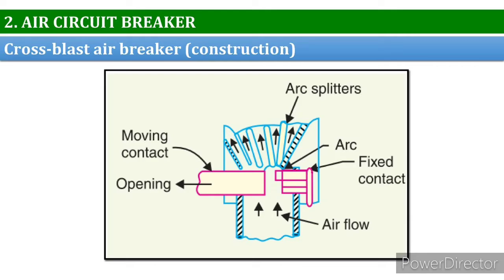When the moving contact is withdrawn, an arc is struck between the fixed and moving contacts. The high-pressure cross blast forces the arc into a chamber consisting of arc splitters and baffles. An important distinction is that the final gap for interruption is large enough to provide normal insulation clearance, so a series isolating switch is not necessary. However, the cross blast design is more complex compared to the axial blast air circuit breaker.